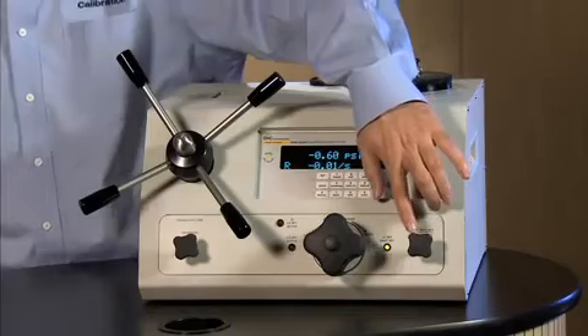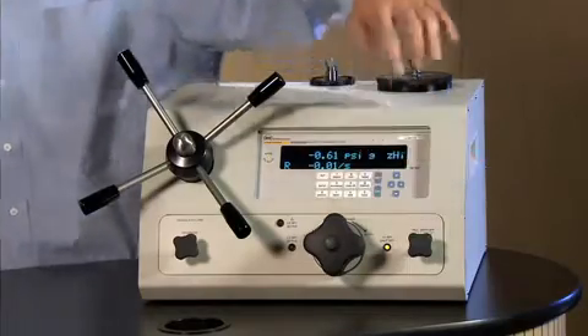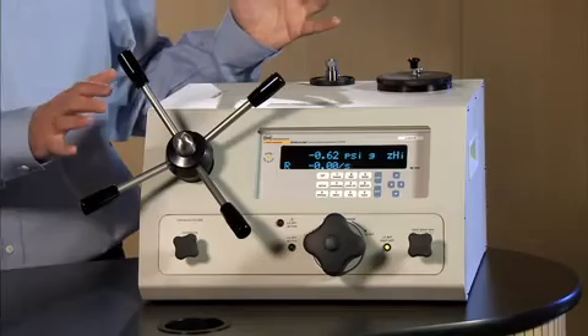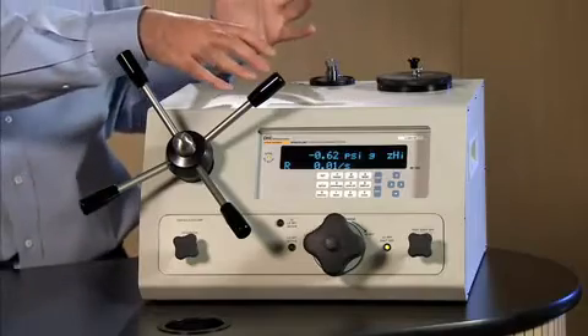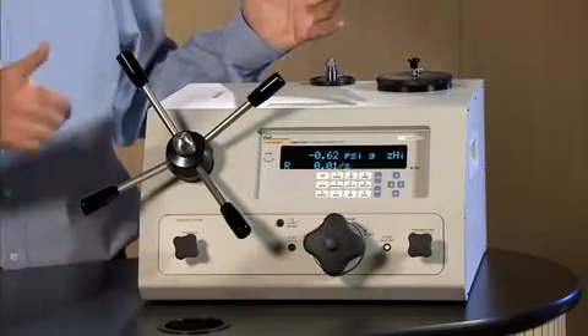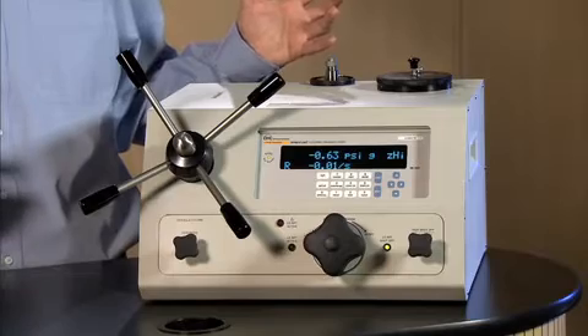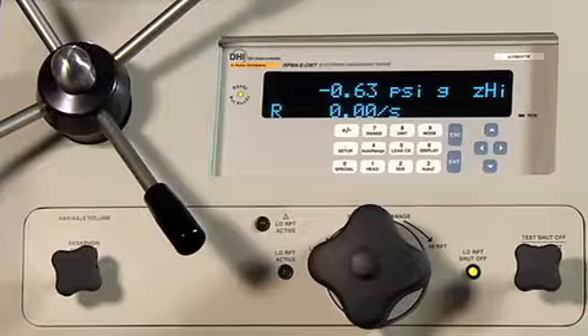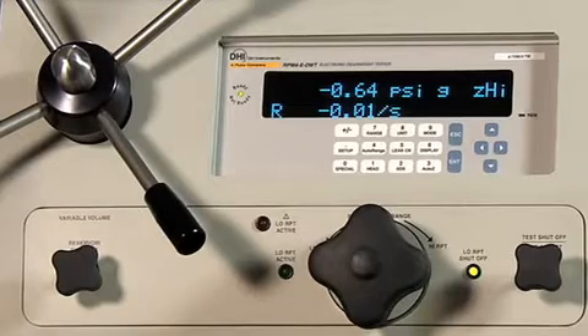Next, we have the test shutoff valve. The test shutoff valve isolates the device under test, your gauge, from the variable volume and the RPM4. This allows you to maintain a pressure on the gauge while pulling more fluid in on the variable volume to give you more capacity for larger volumes in your test gauge.